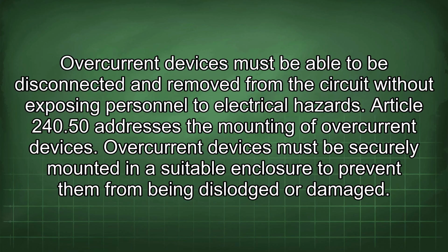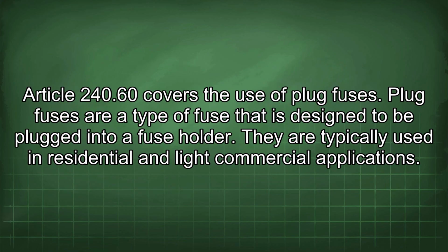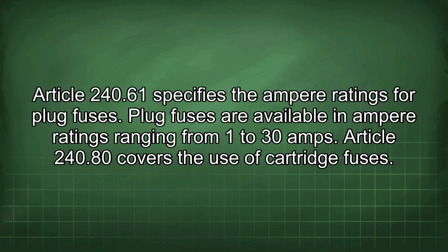Article 240.50 addresses the mounting of overcurrent devices. Overcurrent devices must be securely mounted in a suitable enclosure to prevent them from being dislodged or damaged. Article 240.60 covers the use of plug fuses. Plug fuses are a type of fuse that is designed to be plugged into a fuse holder. They are typically used in residential and light commercial applications. Article 240.61 specifies the ampere ratings for plug fuses. Plug fuses are available in ampere ratings ranging from 1 to 30 amps.